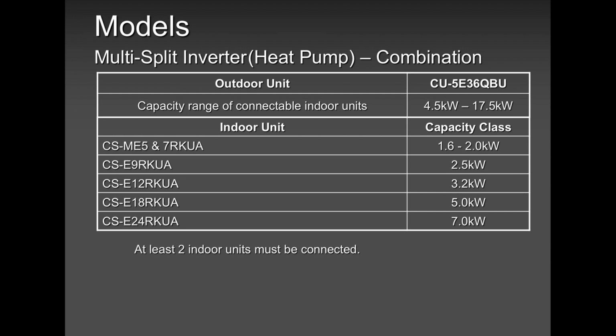So in all our multi-zones, guys, at least 2 indoor units must be connected. Now, Paul and Tony told me 2 units. Okay, I'm going to put any 2 units. No, please don't put any 2 units. You have to maintain minimum and maximum capacity. So 2 units, if you picked a 36,000, for example, and you put two 7,000s, you are at 4 kilowatts, and 4 kilowatts is still under 4.5. So this is not good. Please keep in mind to maintain minimum and maximum capacity. If you put two 9,000s, you're good, because now we are above 4.5 and we have not crossed 17.5 kilowatts.